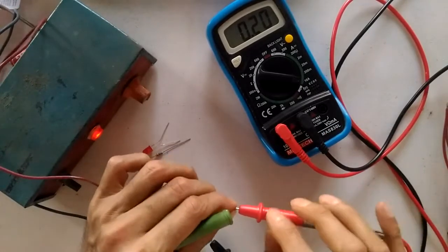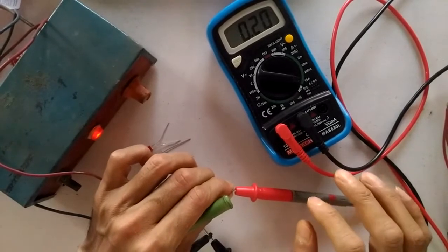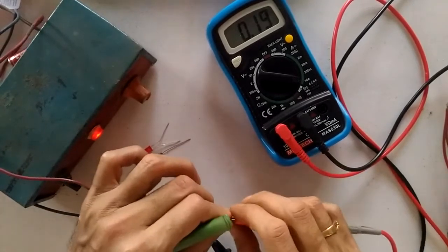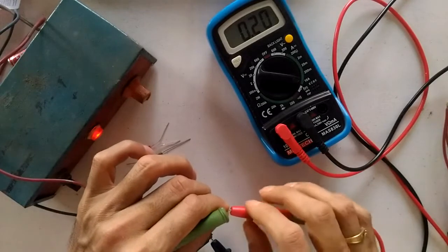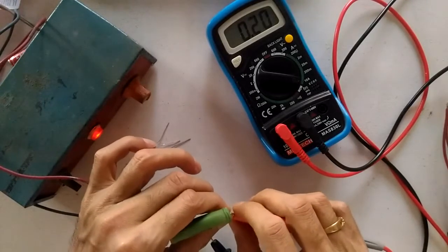So be careful while measuring current. Always start from the higher range unless you are very sure that the current is going to be lower. Then you can work on a lower range. Preferably always start on the higher range.